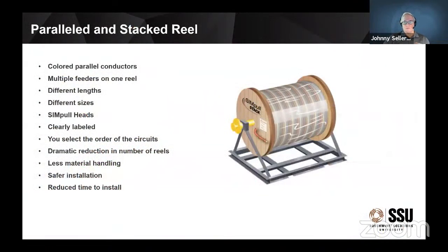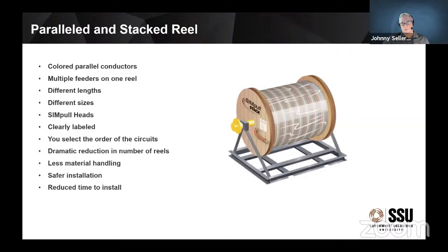Parallel and stack reels — let's talk about what they are. Parallel means we simply take the phase conductors, ABC — your black, red, blue, or brown, orange, yellow, whatever you may have — and instead of having separate reels of black wire, we're going to parallel those conductors together and use colored conductors, putting them on one reel. That reduces the number of reels you have on the job. Colored wire costs exactly the same as black wire. Pretty much the world has moved over to colored conductors, which solves cross-phasing problems when you're terminating in the field.